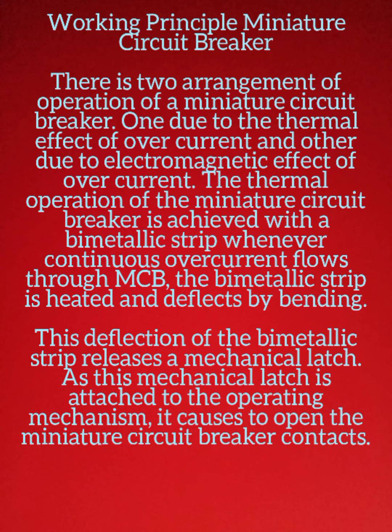Next, coming up to its working principle, there are two arrangements of operation of your miniature circuit breaker. One is due to the thermal effect of overcurrent and the other due to the electromagnetic effect of overcurrent. The thermal operation of the miniature circuit breaker is achieved with the bimetallic strip. When continuous overcurrent flows through the MCB, the bimetallic strip is heated and deflects by bending, as I said in the previous part's diagram. Then this deflection of the bimetallic strip releases a mechanical latch. As this mechanical latch is attached to the operating mechanism, it causes the breaker to open. So whenever the bimetallic strip gets activated due to the temperature, it will initiate the latch and the latch gets opened.